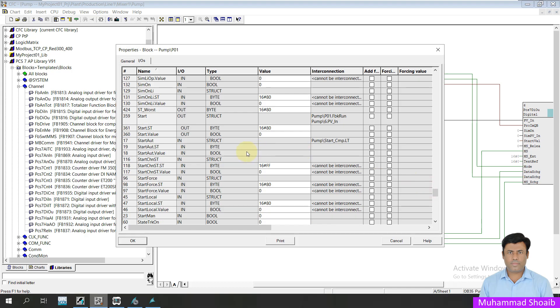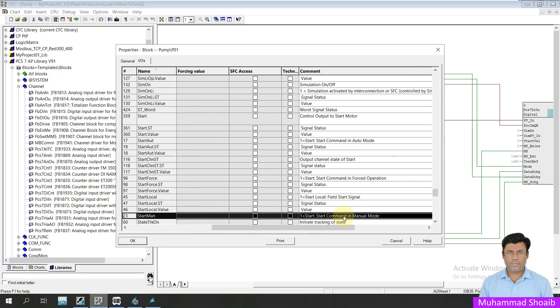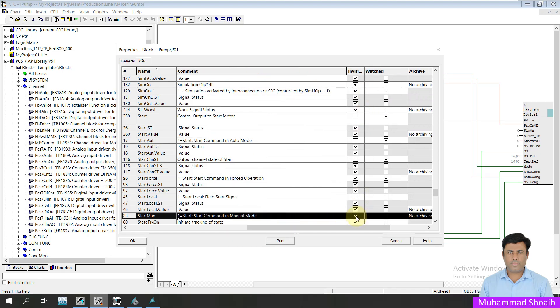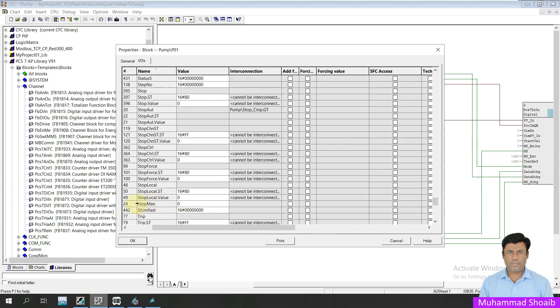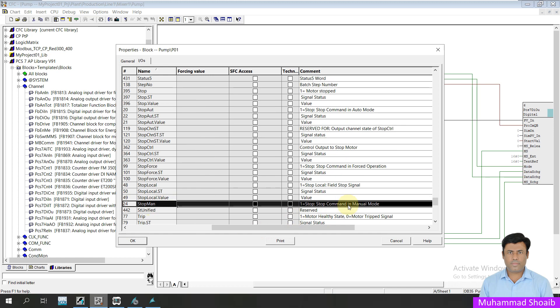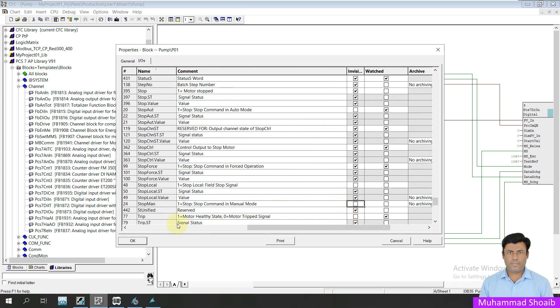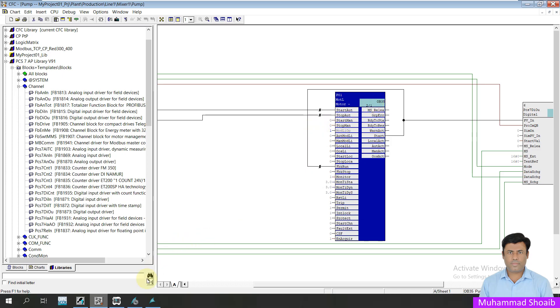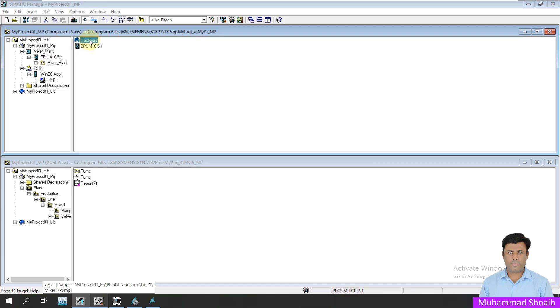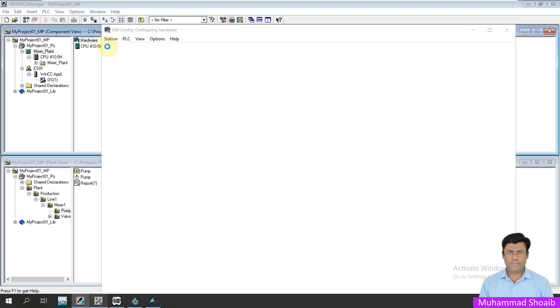Go down and find 'start manual' — this is the start command in manual mode. Uncheck the hidden checkbox so it becomes visible. Similarly, find 'stop manual' — this is the stop command in manual mode — and unhide it as well. Click OK. Now you can see we have two new inputs. Before linking these inputs, we go to the hardware area and open the hardware configuration to add four different signals.